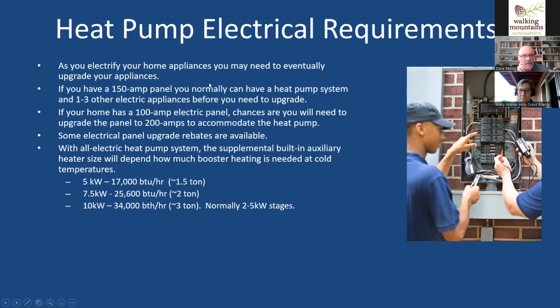Upgrade your breaker—typically if you've got a 150 amp panel, especially with an air conditioner, you can add a heat pump and a little electric strip, or add 1 or 2 electric appliances. When you start to get full electric with all the appliances and the heat pump, etc., then you might have to go up to another panel size.